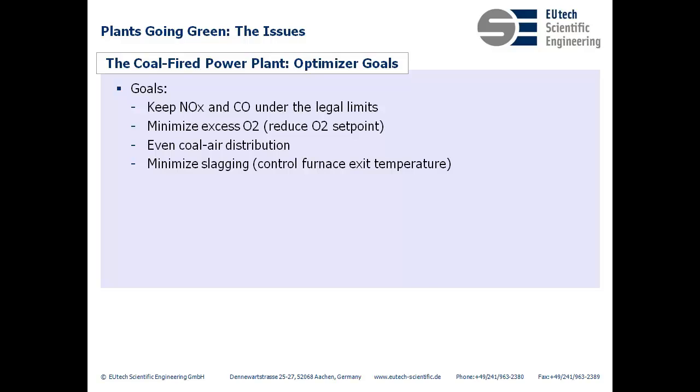If not all of the mills around the boiler are active, this can lead to uneven coal distribution of coal entering the combustion chamber and hence lower efficiency. The optimizer also aims to control the air dampers so that coal distribution inside the boiler is as even as possible.